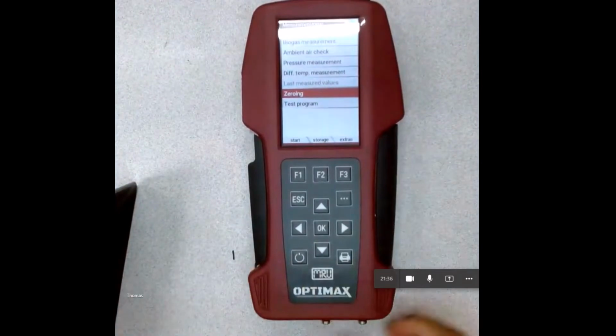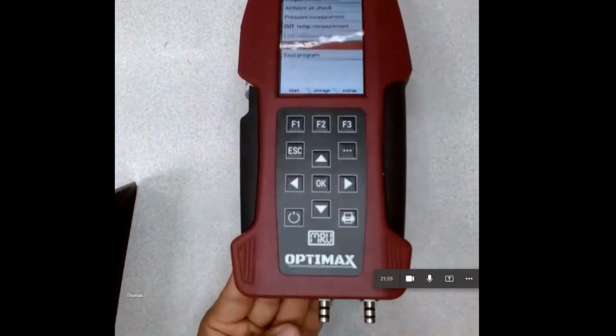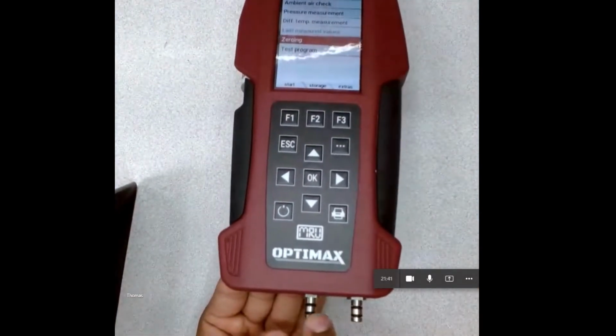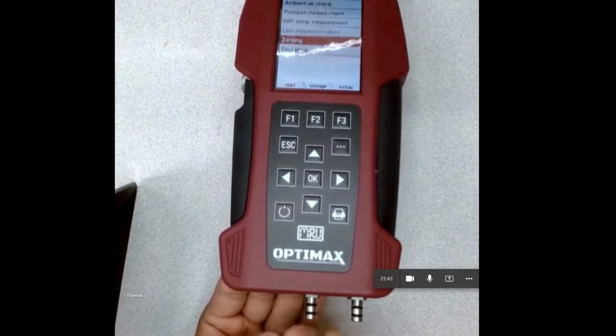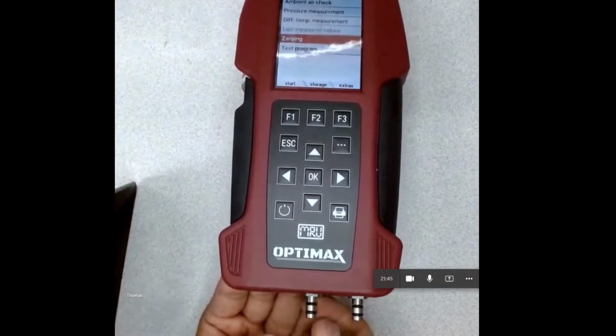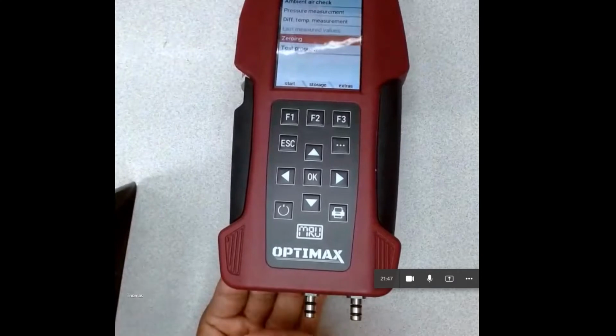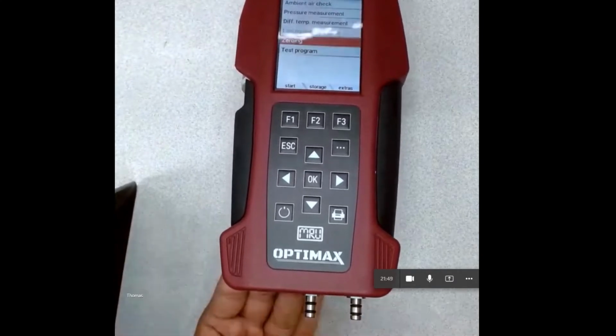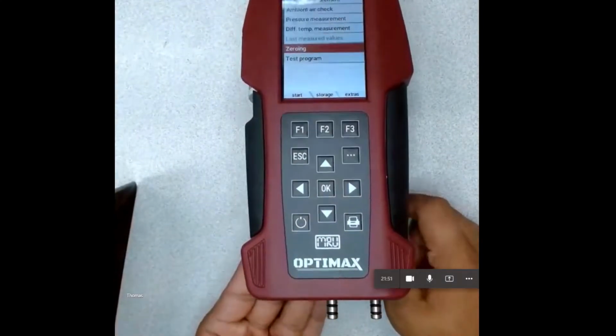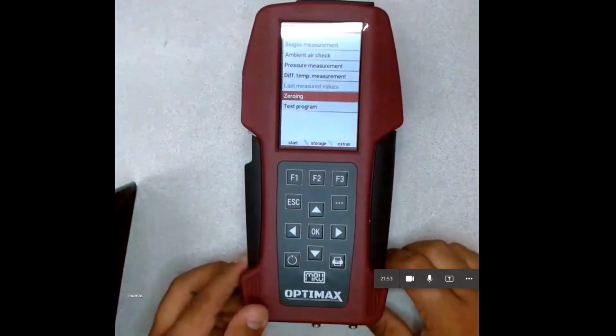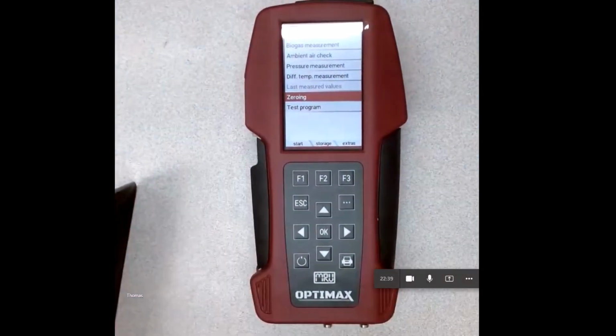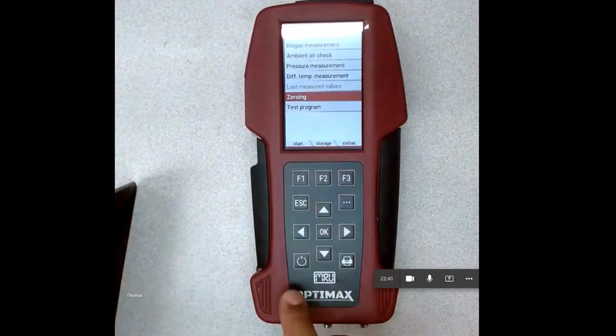And then same goes for the O-rings at the bottom right here. Because remember, to do the pressure test, you have to go to the pressure inlet. So if the O-rings here are messed up, then you'll get fresh air into the leak test. So after it's zeroed, it's ready for calibration.